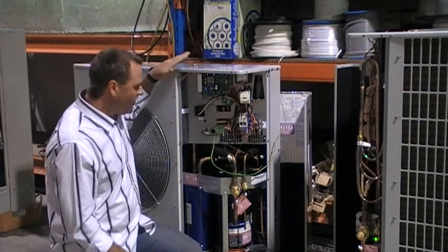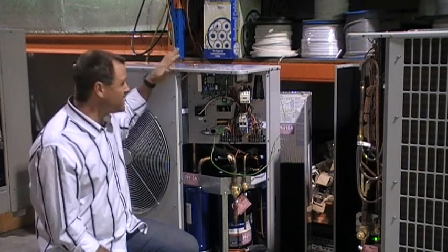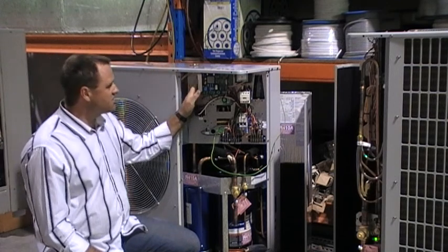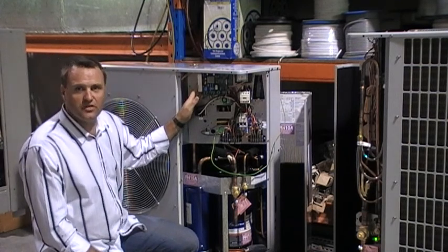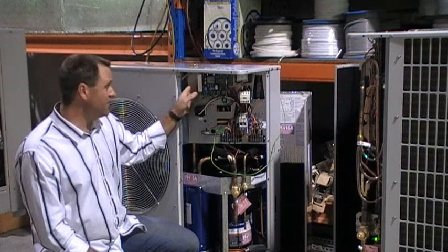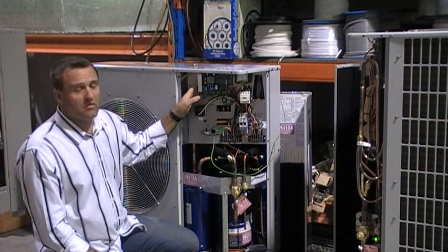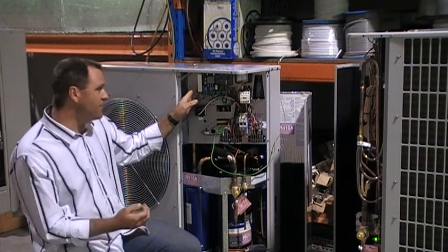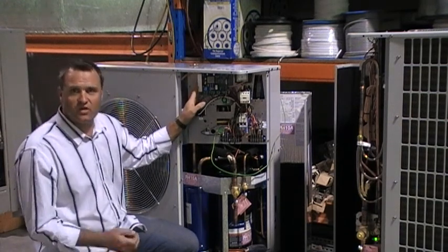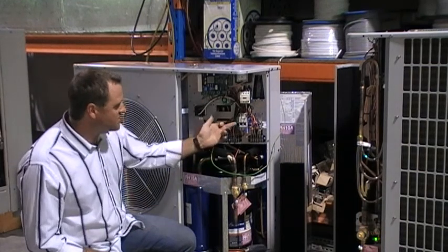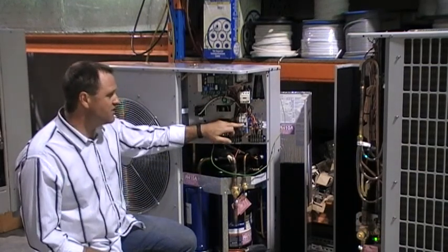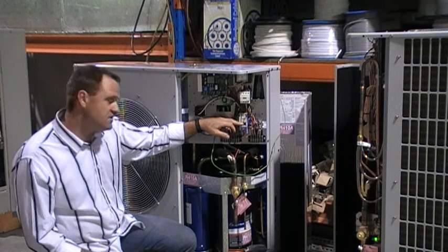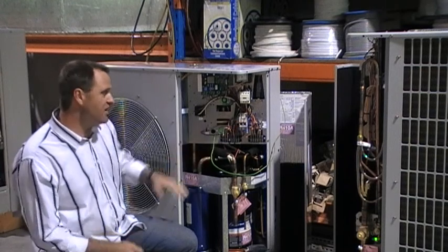One of the advantages of these units, which this is a Temperzone unit, one of the big advantages with a Temperzone is that they use the same PC board for most of their units, so we can actually keep one on the shelf. They're a very reliable board, and I can't really recall vermin ever being a problem with these sort of things, but if they are, look, we keep them on the shelf. One size fits all, so to speak. They also have control circuits built into them to protect the indoor unit and comply with Australian standards, whereas with the Japanese units, that's an extra that we have to put on.